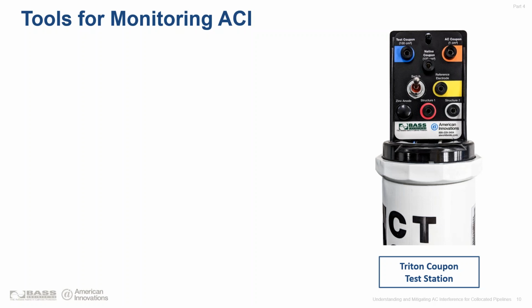Now, above ground, you're going to have the test head, which is pictured here. This is going to be your access point into that section of the pipeline. From the test head, you can take all of the measurements you need to not only check your ACI threat, but you can also check to see whether or not you're applying enough cathodic protection at a certain area.